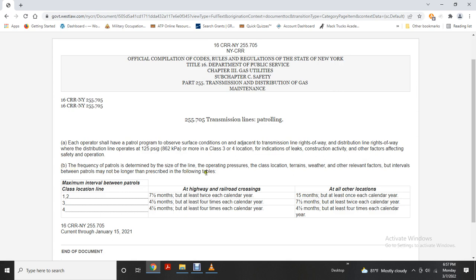Intervals between patrols are prescribed in the following table. Class 1 or 2 locations: at intervals not exceeding 15 months, but at least once each calendar year. Class 3: 7.5 months, but at least twice each calendar year. Class 4: 4.5 months, but at least 4 times each calendar year.